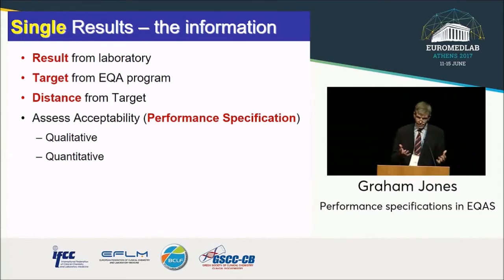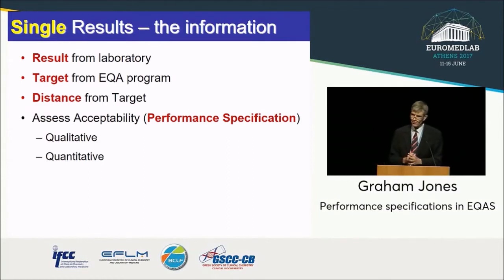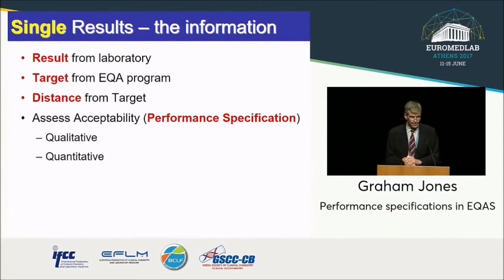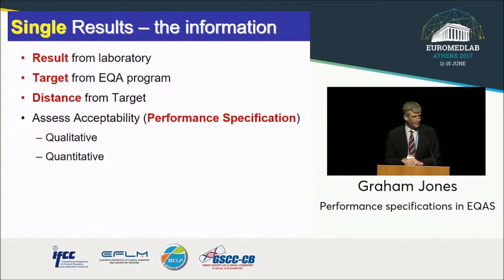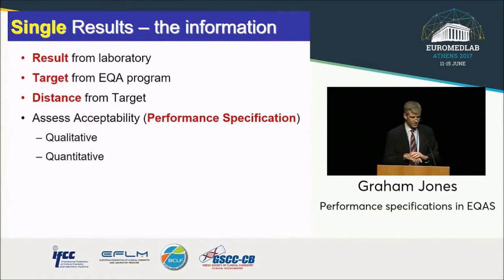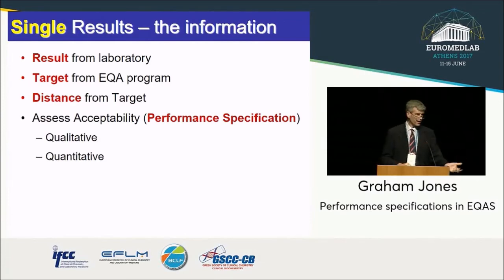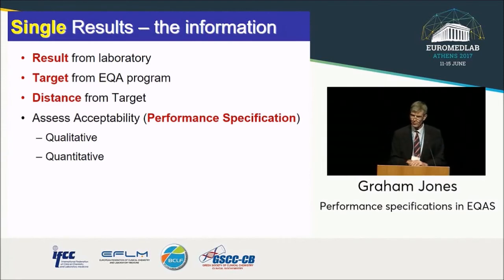When you look at an EQA report coming back to your laboratory, there are several discrete pieces of information you have in front of you: the result you generated, the target from the EQA program, and you can then calculate how far you are from that target. Assessing the size of that distance against a performance specification allows you to say whether you're meeting your needs.